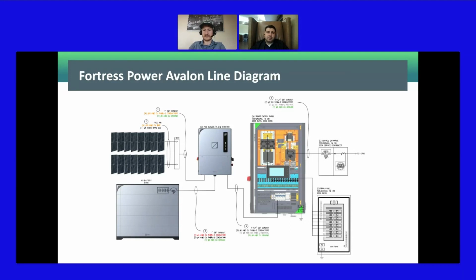In terms of DC coupled and AC coupled, the inverter, each of them, doesn't matter whether it's 7.6 or 11.4, has 4 MPPTs, each completely independent of each other. Combined, they can accept an input of 18 kilowatts, so each MPPT accepts 4.5 kilowatts.